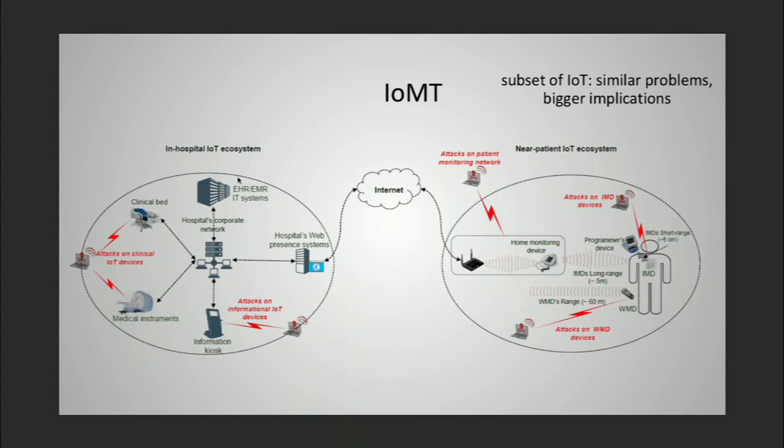And there are a lot of attack vectors everywhere. For example, with implantable devices, recently there's been this trend of having home monitoring devices where you have a patient that has a pacemaker implanted in them, and then this device communicates with another system that is installed in the patient's home. They talk over a wireless protocol, and then say once per day, the pacemaker sends some diagnostic data to the home monitor, which then sends that to the cloud.